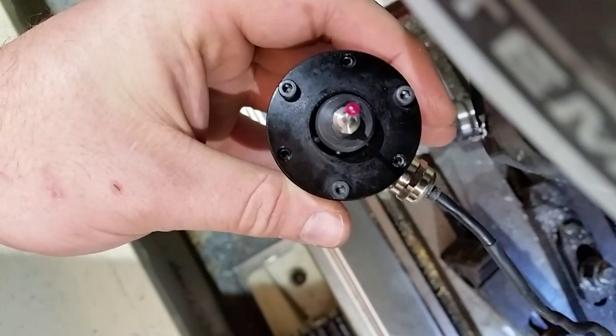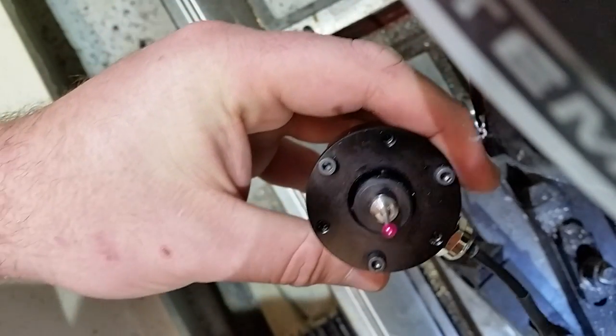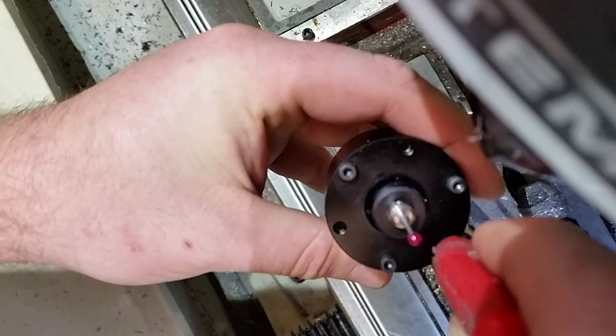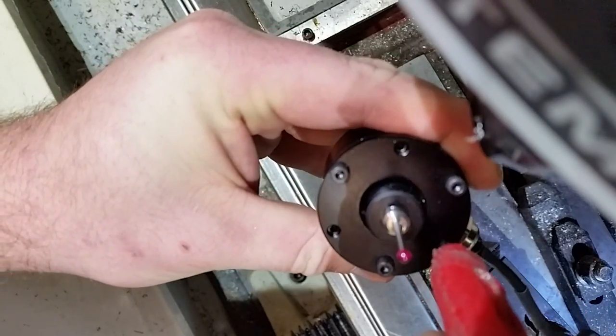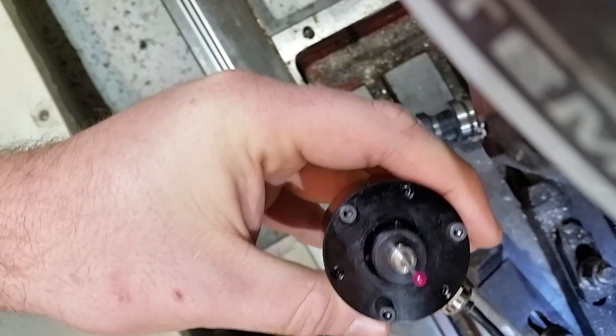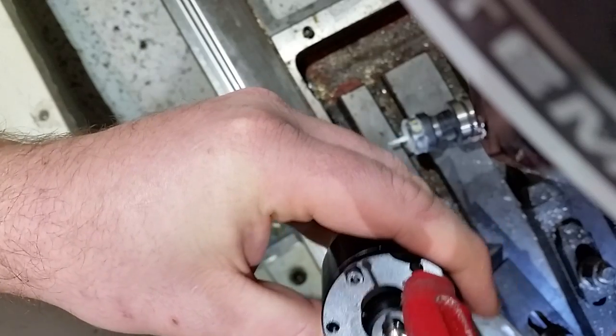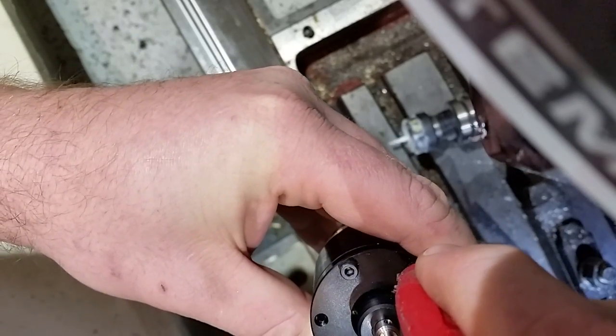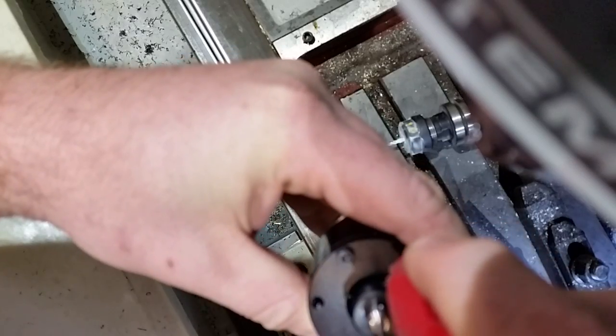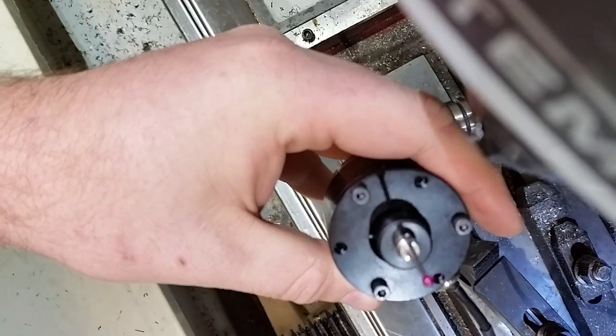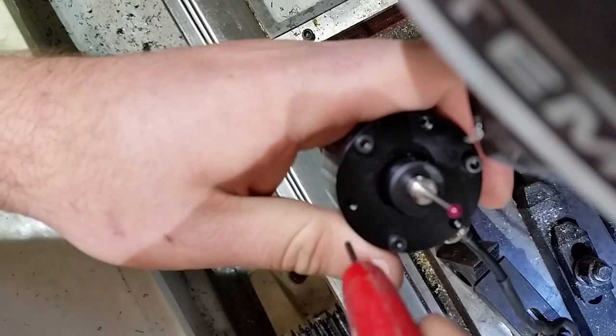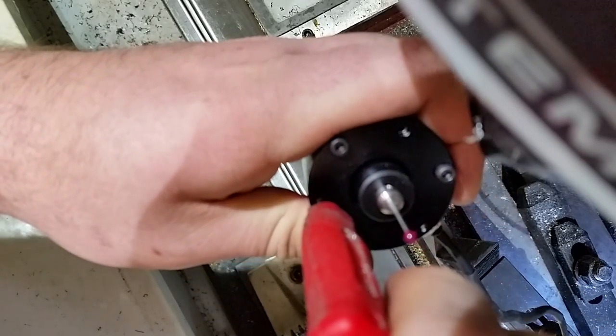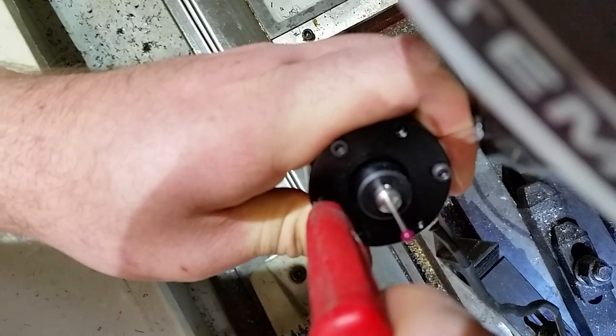Alright, looking at the bottom of this, screw 1 needs to go in 0.01. So, screw 2 needs to come out 0.03. Screw 3 needs to go in 0.02. Alright, we're ready to retest it.